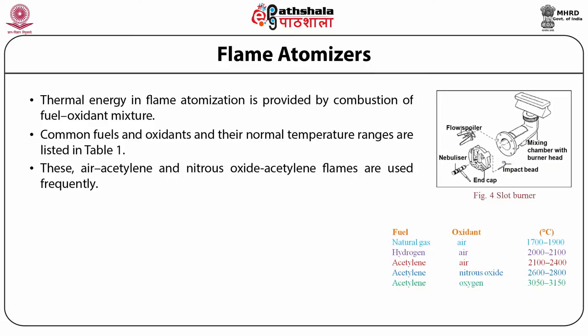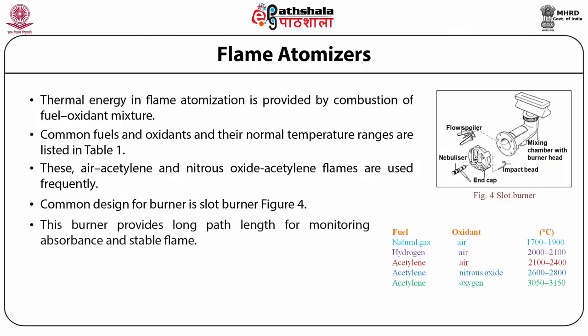Normally, the fuel and oxidants are mixed in an approximately stoichiometric ratio. However, a rich fuel mixture may be desirable for atoms that are easily oxidized. The most common design for the burner is the slot burner as shown in figure 4. This burner provides a long path length for monitoring absorbance and a stable flame.